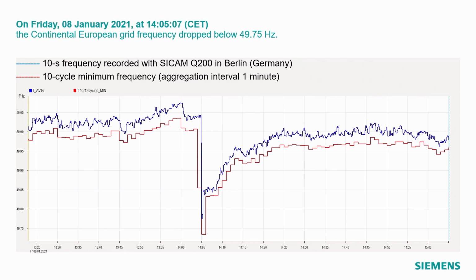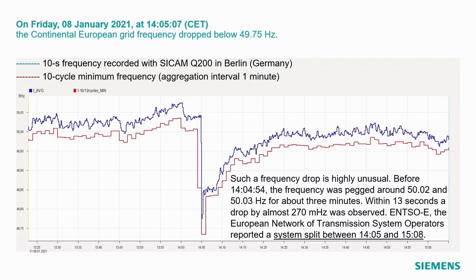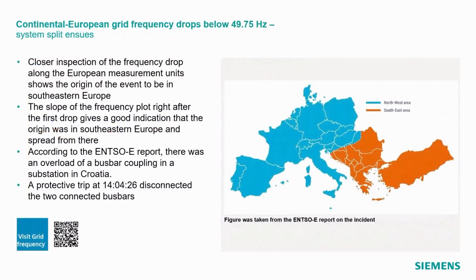The frequency was stable before the problem occurred. The frequency was around 50.02 and 50.03 Hertz. And then a frequency drop happens within 13 seconds, and the frequency went down by 270 millihertz. Such frequency drops are very, very seldom. And the problem is who was responsible for this event here. Let's go to the next slide.